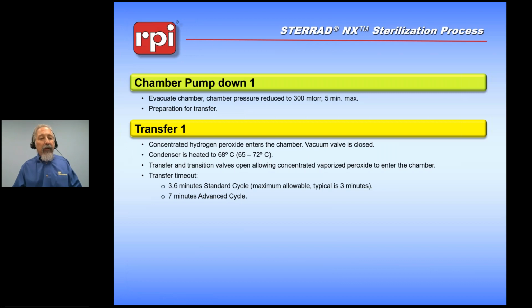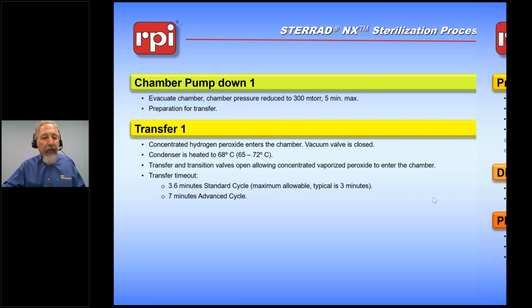Chamber pressure. We need to look at the chamber to make sure that when we transfer the condensed hydrogen peroxide, the pressure in the chamber is lower than the pressure in the vaporizer condenser assembly, and that allows the peroxide to move from the higher pressure to the lower pressure, thus filling the space within the chamber and spreading out throughout all the various spots we're trying to reach.